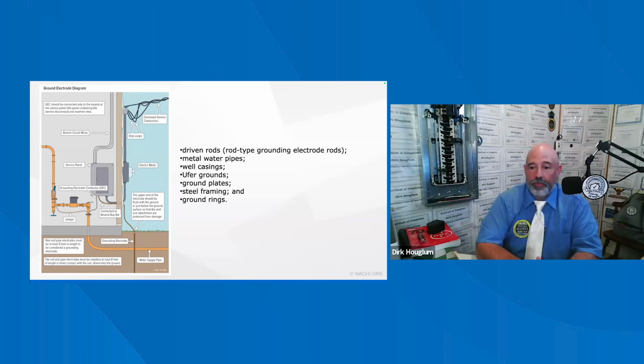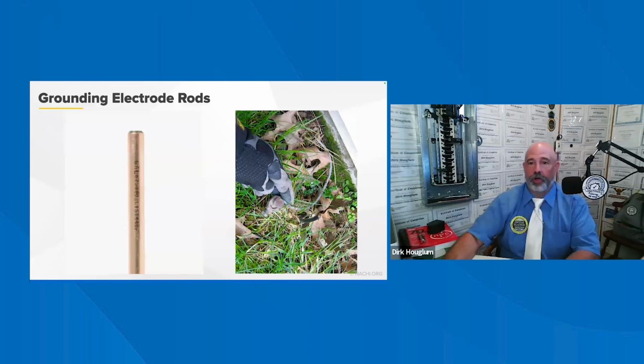And if you want to reference that, that's at 250.56 in the NEC. Gas piping should not be used as a grounding electrode for safety reasons, but in most areas, gas lines are required to be bonded to the electrical system if they are likely to become energized. Very important to know.